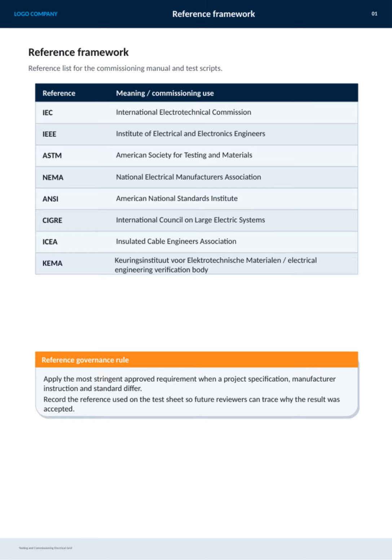On this slide, we focus on the reference framework for testing and commissioning the electrical grid. These references are essential because they guide the creation of commissioning manuals and test scripts, ensuring everything is done correctly. We rely on well-known standards and organizations such as IEC, which stands for the International Electrotechnical Commission, IEEE, the Institute of Electrical and Electronics Engineers, and ASTM, the American Society for Testing and Materials. Other important bodies include NEMA, the National Electrical Manufacturers Association, ANSI, the American National Standards Institute, and specialized groups like CIGRE, ICEA, and KEMA, which is an electrical engineering verification body.